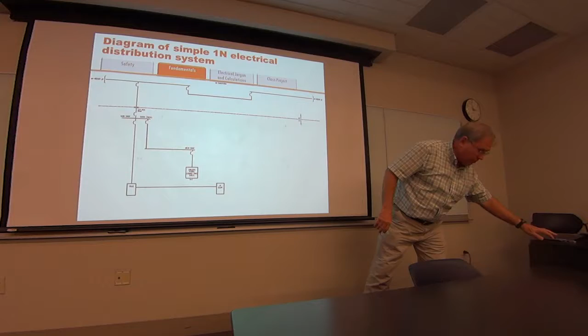So that's with no UPS, and I added this down here. This is a dual corded system. It has two inputs, they convert it to DC. So if I lose one input, all the load shifts over to the other input and vice versa. They usually run about 50-50.